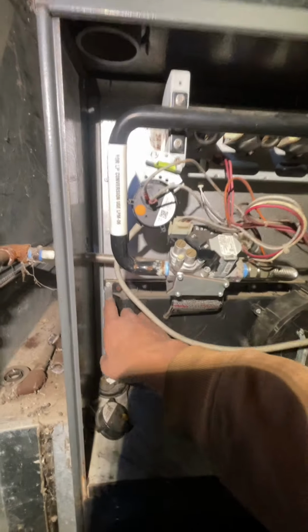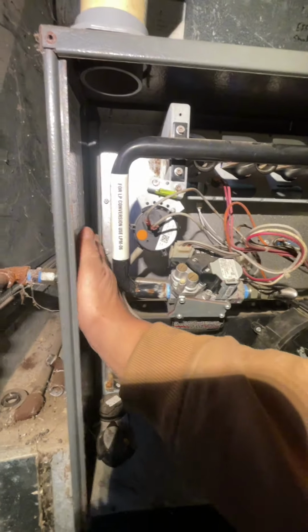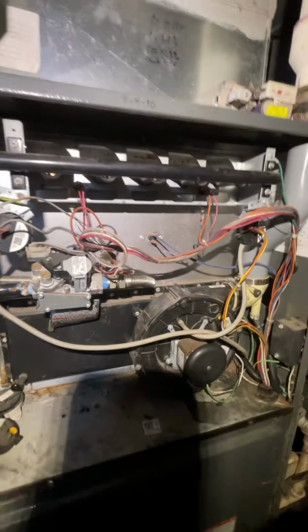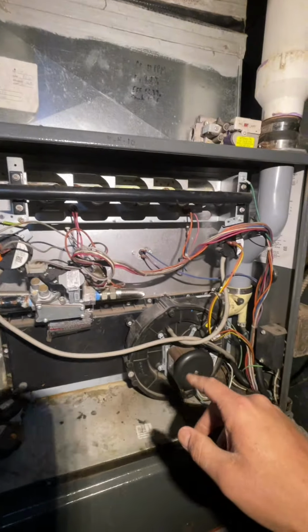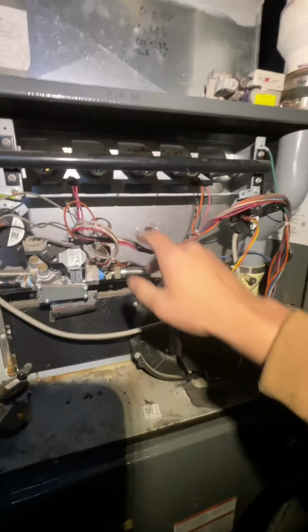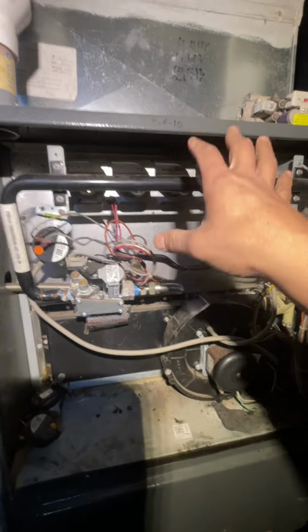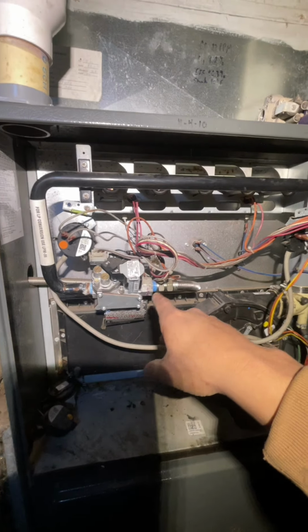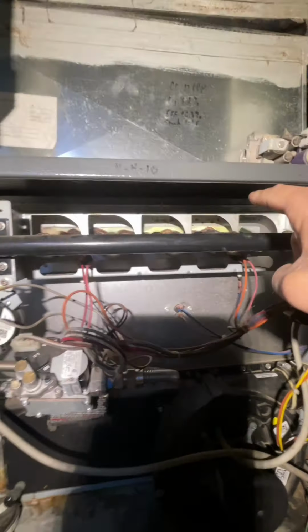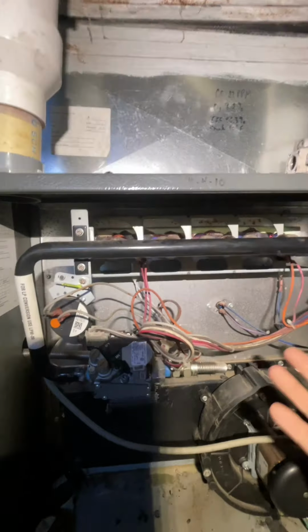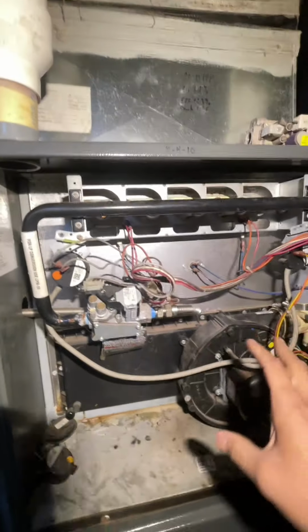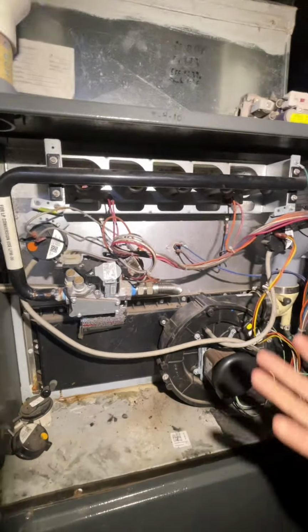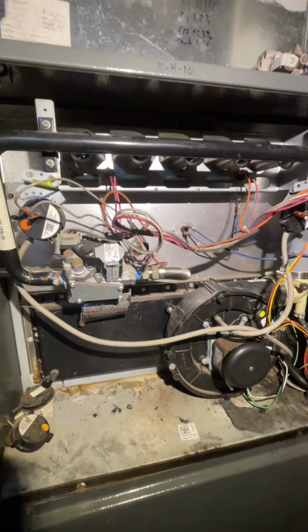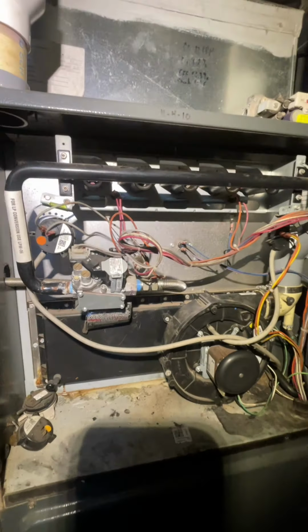Essentially we have to take this whole plate off - you can see the plate here, this is all the heat exchanger, the whole thing. First you take the initial stuff off, take the inducer out, take the burn chamber out by disconnecting the gas. Then there's screws on the bottom and top of the burn chamber - you unscrew that, it all comes out, and we expose the heat exchanger, then we can pull it out. It's not the easiest job, but it's not the end of the world.